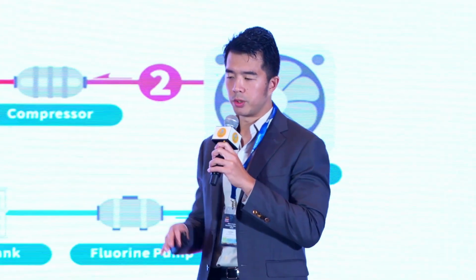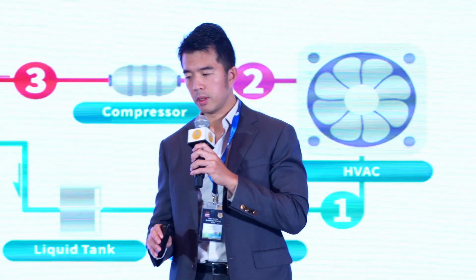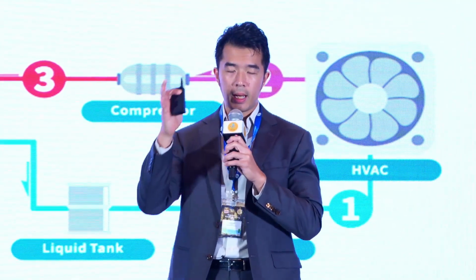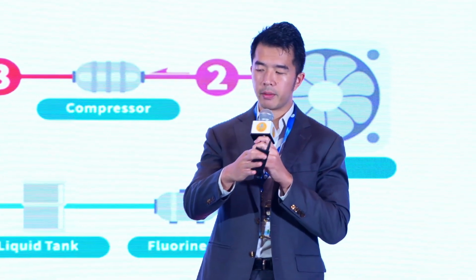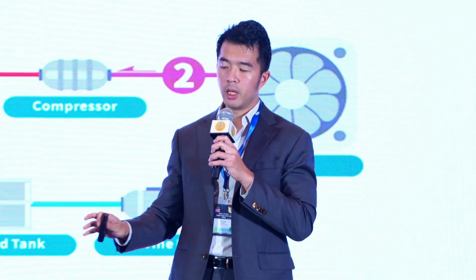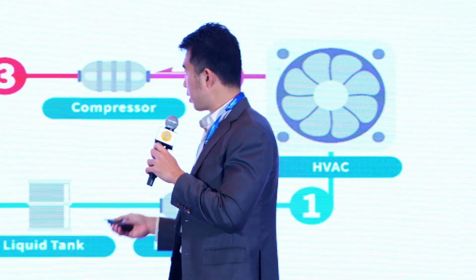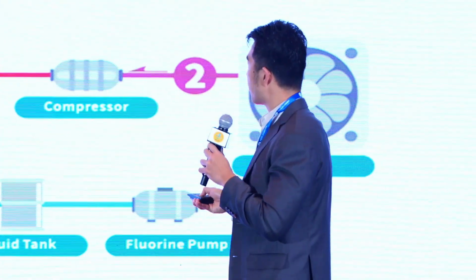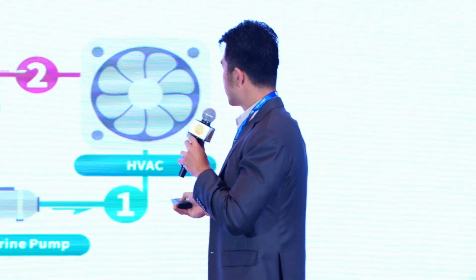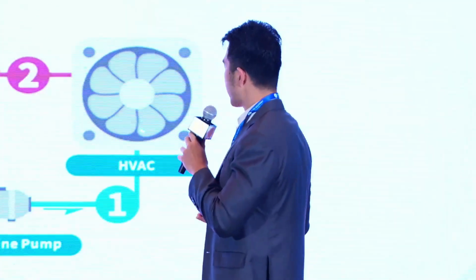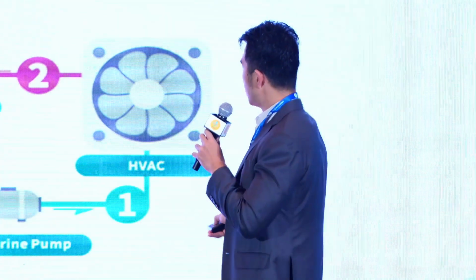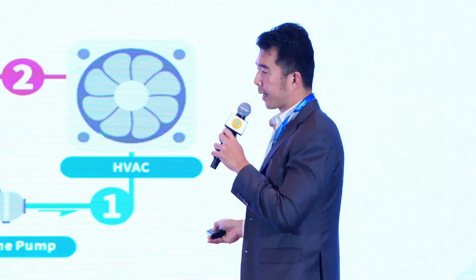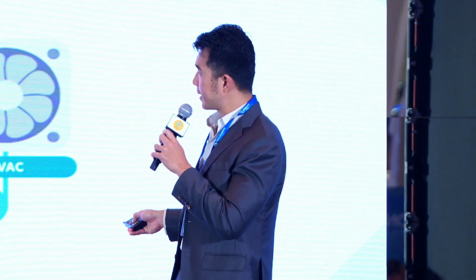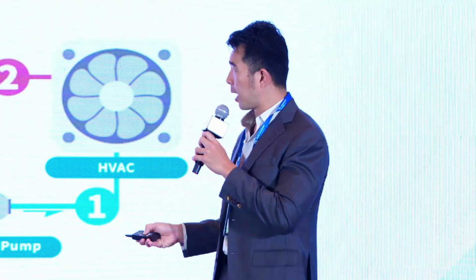So how does Suntar actually do it? Our solution sits at the supply side to the cooling towers. On the cooling tower side, people will be very familiar: the cooling tower goes to the HVAC to help cool the building for your data centers. Where we come in is that we do the makeup water supply.